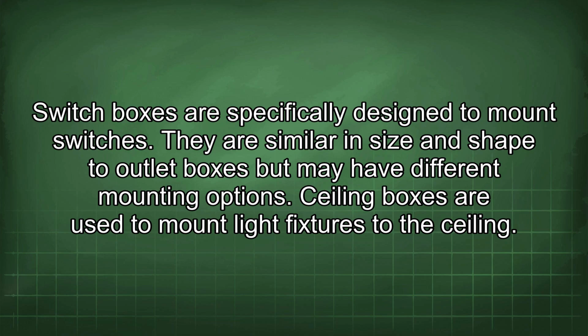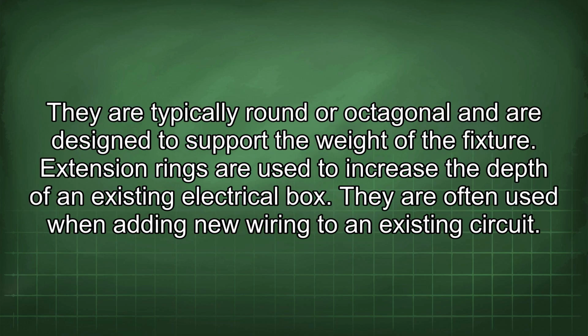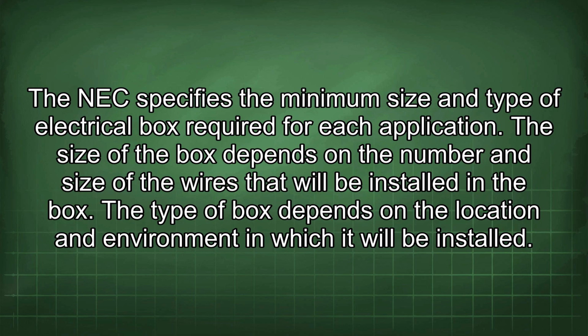They are similar in size and shape to outlet boxes but may have different mounting options. Ceiling boxes are used to mount light fixtures to the ceiling. They are typically round or octagonal and are designed to support the weight of the fixture. Extension rings are used to increase the depth of an existing electrical box. They are often used when adding new wiring to an existing circuit. The NEC specifies the minimum size and type of electrical box required for each application. The size of the box depends on the number and size of the wires that will be installed in the box.